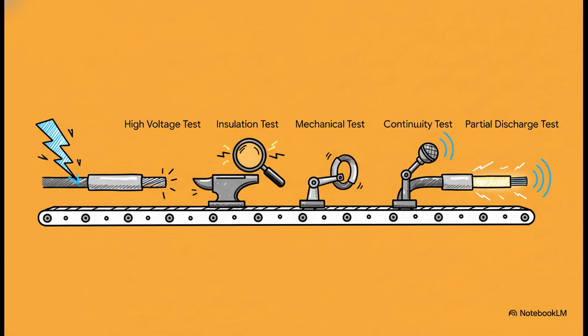They get hit with a high voltage test, or hipot test, which basically zaps the cable to try and find any tiny weakness in the insulation before it becomes a huge problem out in the real world. The insulation resistance test makes sure not a single volt of electricity is leaking out where it shouldn't. A continuity test is simple but critical. It confirms the conductor is one perfect, unbroken line from end to end. Then come the really brutal mechanical tests. They get bent, crushed, and pulled to simulate a lifetime of abuse. And for those high-power cables, a partial discharge test can find microscopic flaws inside the insulation that could grow into a catastrophic failure years down the road. It's an incredibly thorough process.